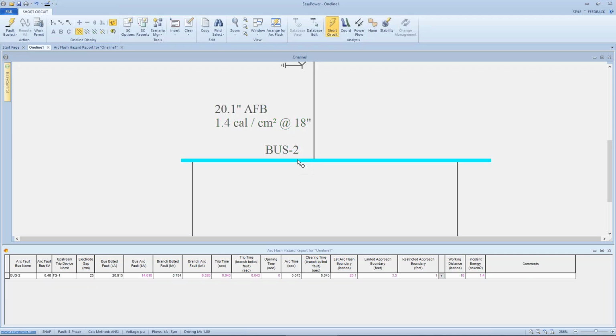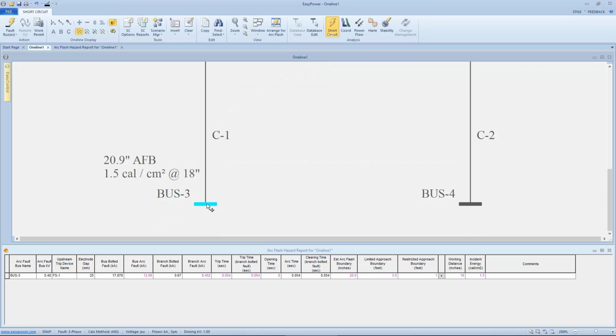So as I double click on bus 2, I see it's a 480 volt bus. It's a fuse as a protective device. The electrode gap as we defined it was 25 millimeters. We already knew the available current was 20,915 amps. According to the IEEE equations, the maximum current an arc will draw is 14,018 amps for this condition, this fault. According to the data sheet, that fuse will blow under these conditions in 43 milliseconds. We put all that in the IEEE equations. We get an incident energy of 1.4 calories and a working distance of 18 inches, and the arc flash boundary is 20 inches. Let's go down to bus 3, double click to fault it.